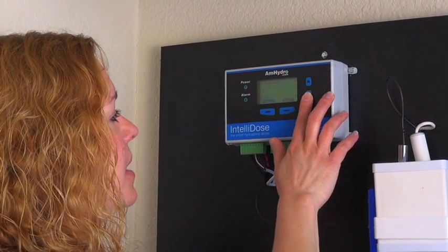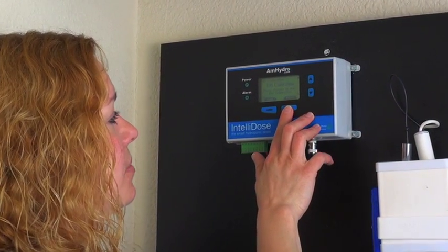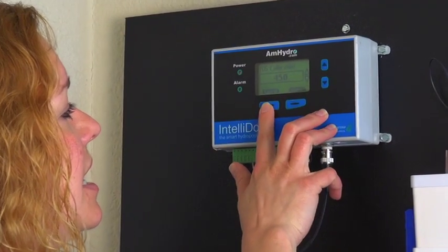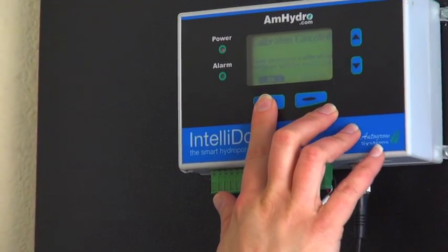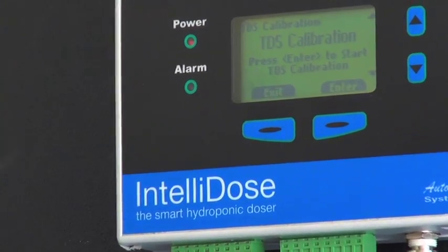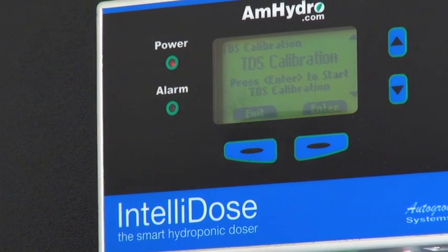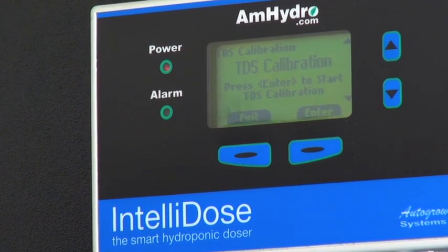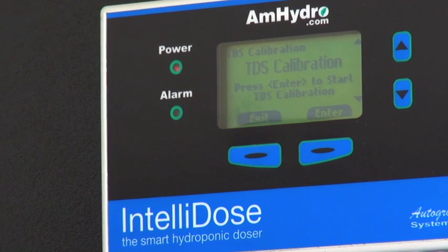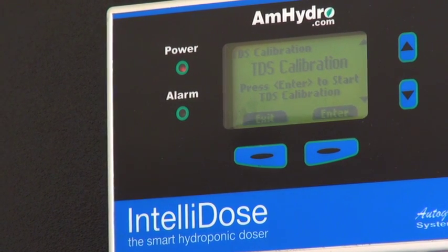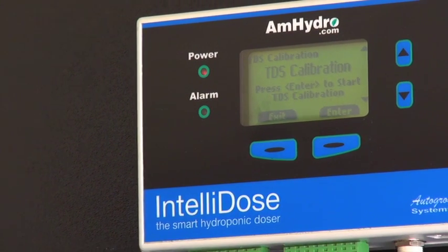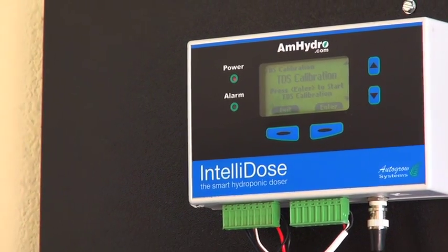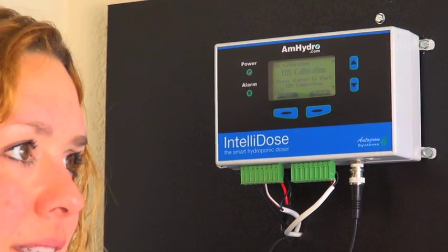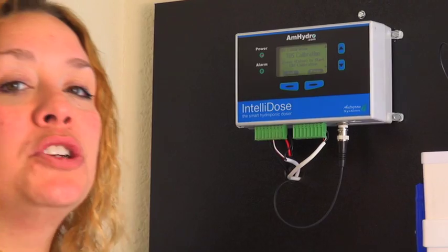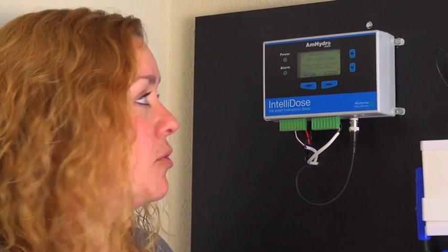After you calibrate your pH, then we have our TDS calibration. So the TDS calibration is a little bit different in the way that the controller works. Because TDS has multiple scales throughout North America and Europe, we actually like to calibrate the unit in EC because then we know it's always calibrated to the same amount. And then when you switch over to TDS, it makes the conversion for you.